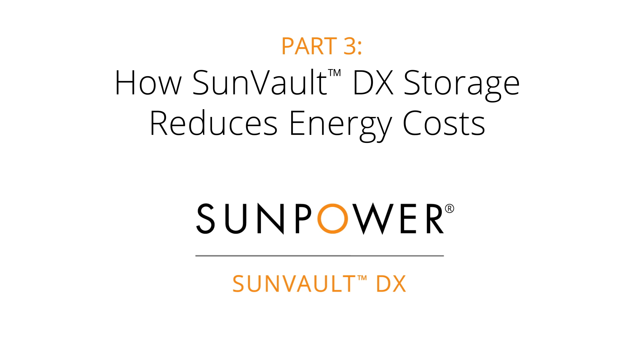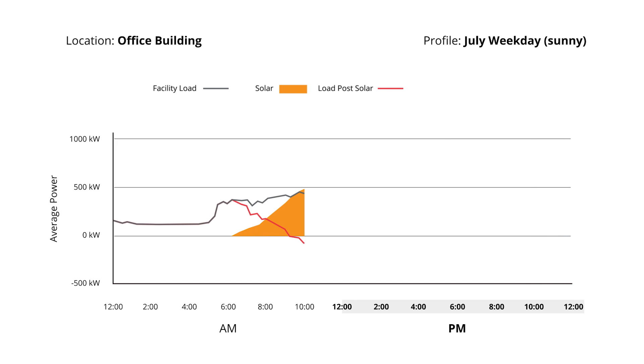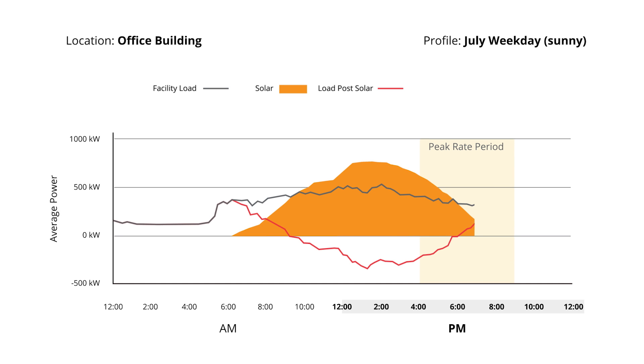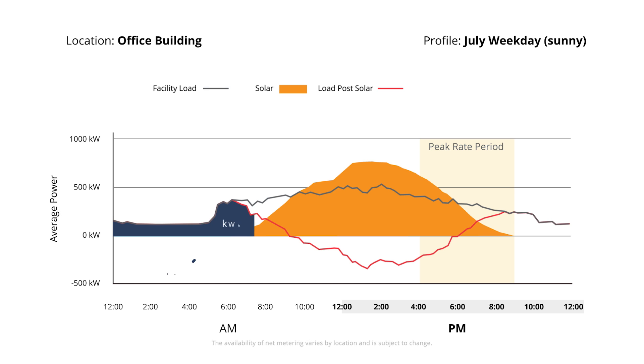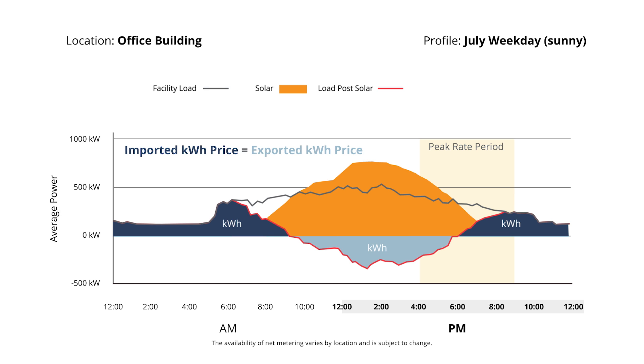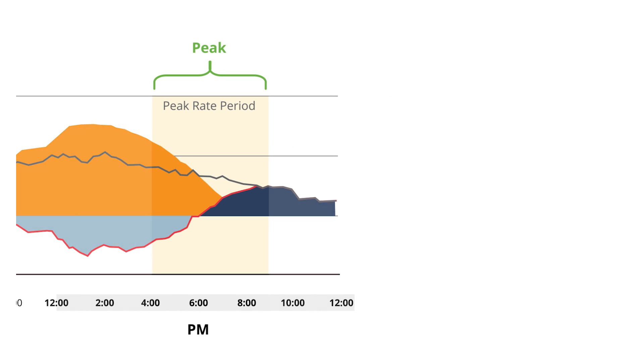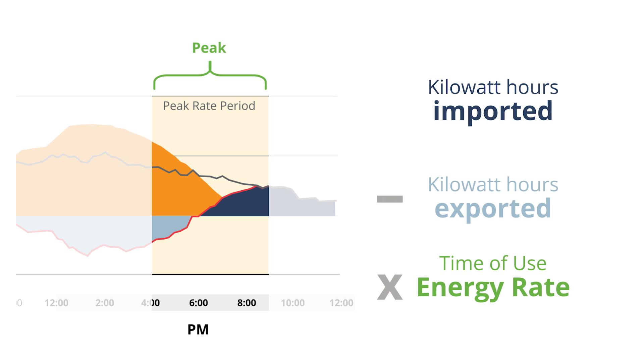Another way customers can save money with Sunvault DX storage is by shifting when they buy energy from the grid over the course of a day. Let's reexamine the load graph we used for demand charge savings. Instead of focusing on demand, we're looking at the amount of energy pulled, or imported, from the grid, as well as the energy sent back or exported to the grid via net metering over the course of this typical July weekday after solar has been installed. This energy is measured in kilowatt hours and is generally represented by the areas above and below the red load post-solar line and the zero kilowatts average power line. This utility offers full retail net metering, which means the import and export prices for electricity are exactly the same. The utility applies a different rate for electricity during the peak and off-peak time of use periods, so the total cost of energy for each period equals the amount imported minus the amount exported, multiplied by that period's energy rate.